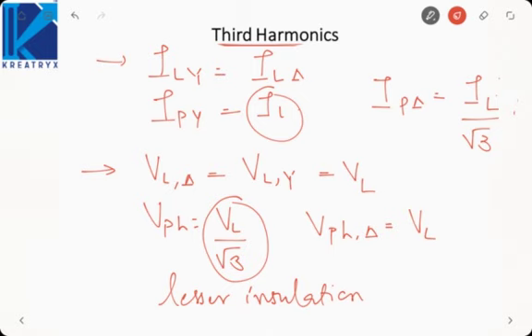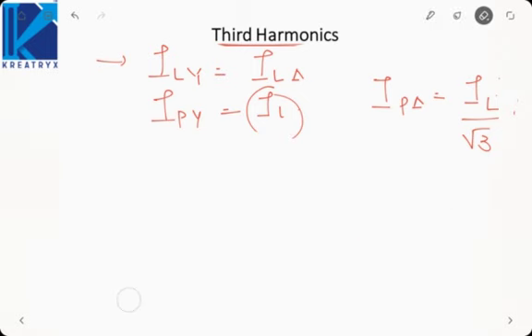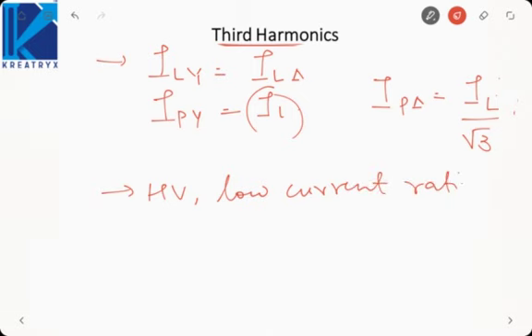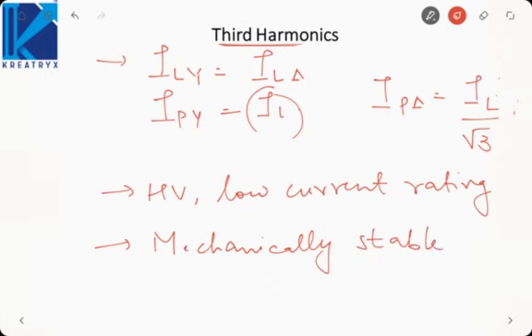The reverse of this we studied in delta-delta. There I told you that the area of cross section of conductor in delta-delta connection is 57.7% as compared to star-star connection. Here I am just saying the reverse. Star-star connection requires thicker conductors as compared to delta-delta connection. So this type of transformer will be used for high voltage, low current rating. If we keep insulation and area same, this transformer will have higher voltage and lesser current. So it is used for high voltage, low current rating, and it is mechanically more stable. Since it uses thicker conductors, its balance is better as compared to delta-delta connection. So it is more robust. So this is about the rating and the physical stability of the transformer.